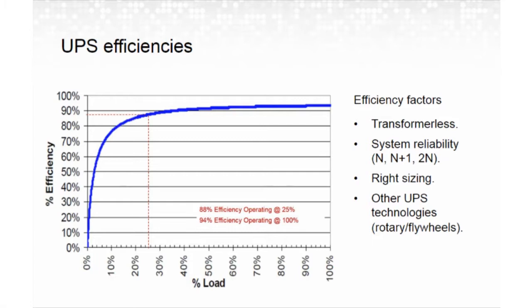Some of the factors that are involved in the efficiency, again, as I said, are transformerless or new technologies, which drive the efficiency up. But there's also the reliability of the system or redundancy you build into a system. For, say, a data center that may have an N+1 UPS for maintenance or reliability, or a 2N UPS, in an N+1 system you may have a UPS system that's sitting unloaded at 0% load, which is going to be very inefficient, or a 2N UPS where there's an A and a B system.